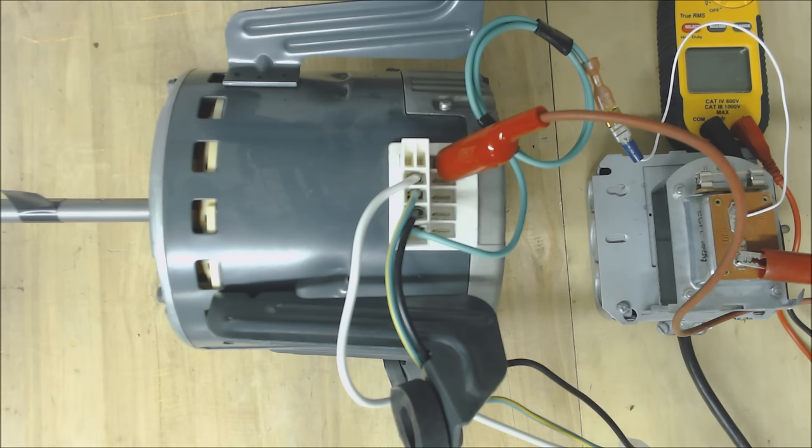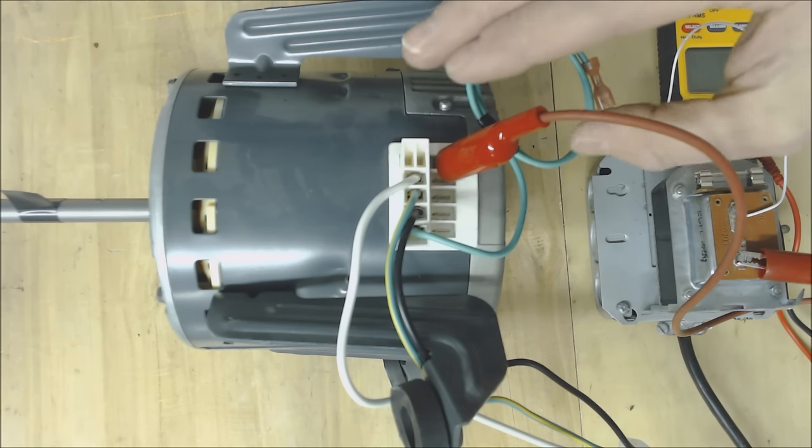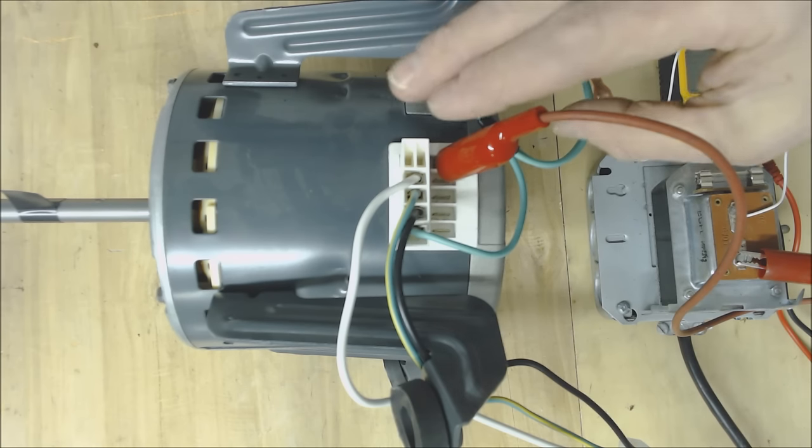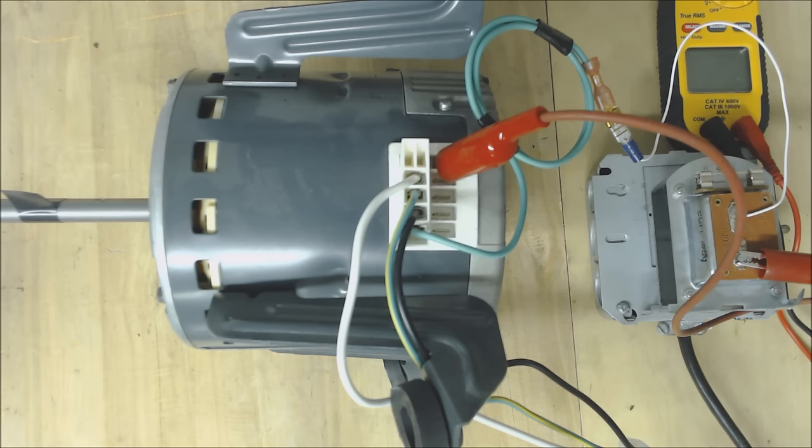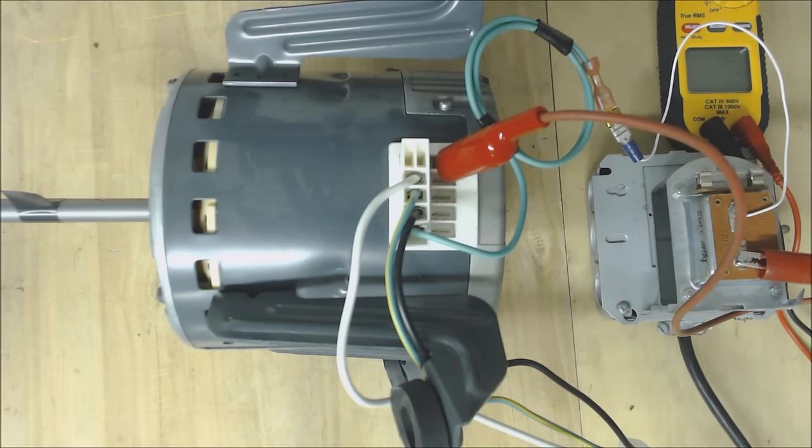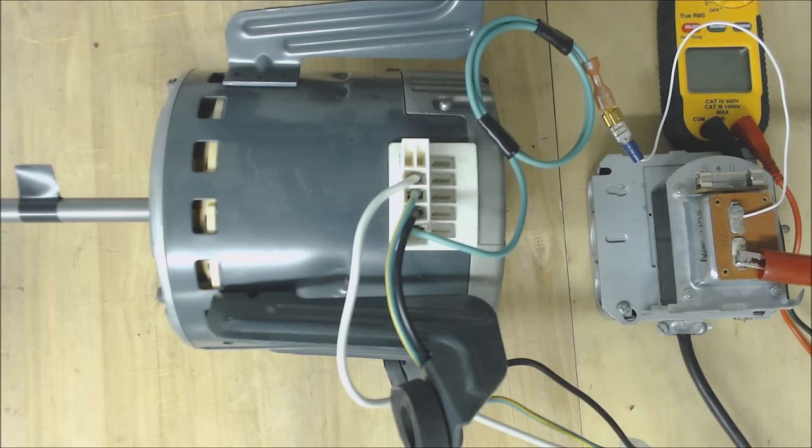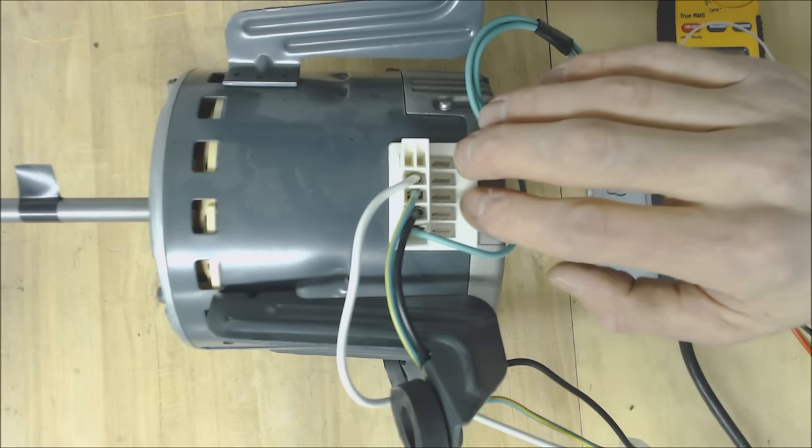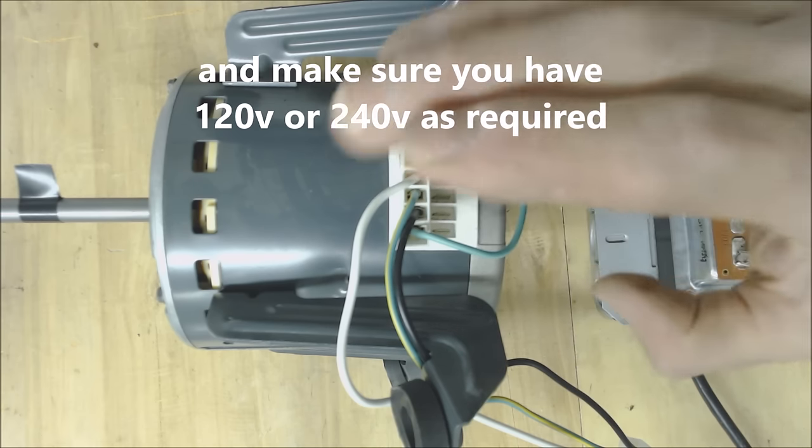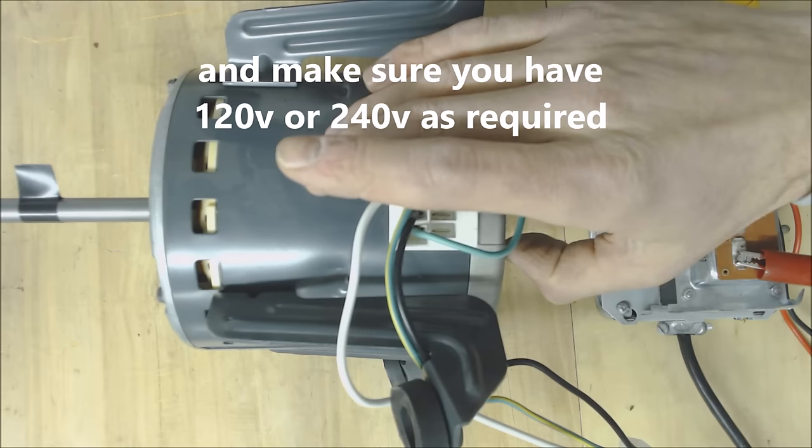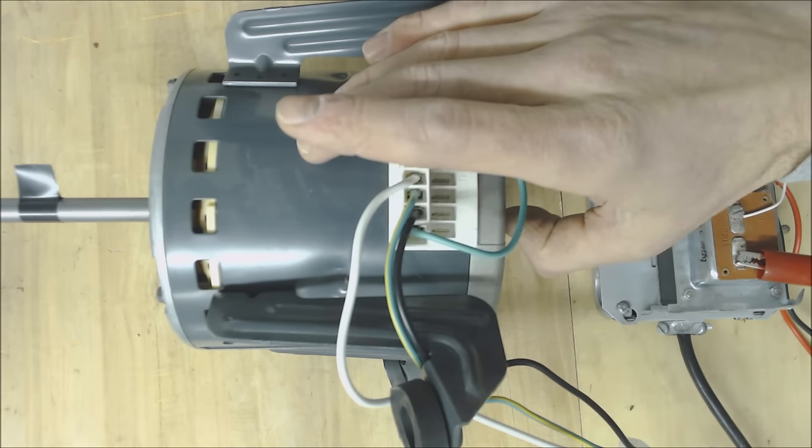just for safety and you don't want to have your hands back in the blower motor area. So once all your electrical connections are connected then you can turn the power on to your furnace or air handler in order to check to see if the blower motor is going to turn on. As long as you know that you're sending 120v or 240v to this and the motor is not spinning then you can move on to the next step.